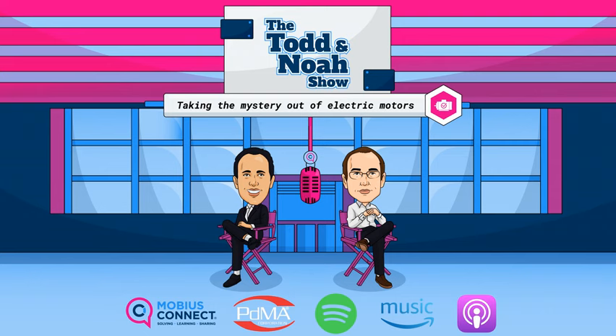Well, this armature had a large burnt hole in the side of it. It had obviously blown. It was the second time it had blown in just the period of 1 year, right? So imagine the cost. We're talking approaching millions of dollars in repair and transportation costs and permits and all that kind of stuff. And you know what the problem was? In the power circuit. It wasn't the motor. It wasn't the power quality. The cable feeding the motor was underground and completely submerged.